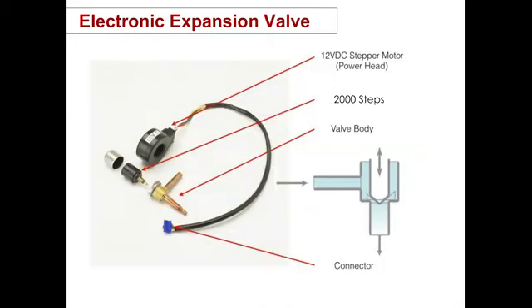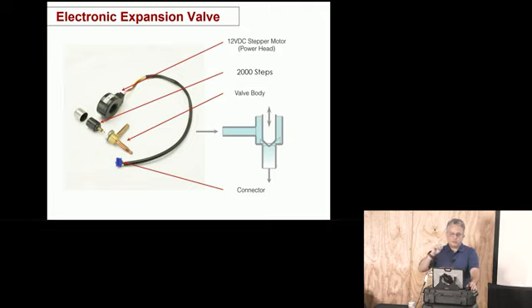Here's a breakdown of an expansion valve. You have typically a 12-volt DC power head. You have the valve body. The stepper motor can go 500 steps or 2,000 steps, depending on what it's doing, how big the system is, and where it is applied. If you think about a thermal expansion valve, it's very slow responding and not very finite in its control. Would you agree with that statement? So with a stepper motor, you just have much more control.